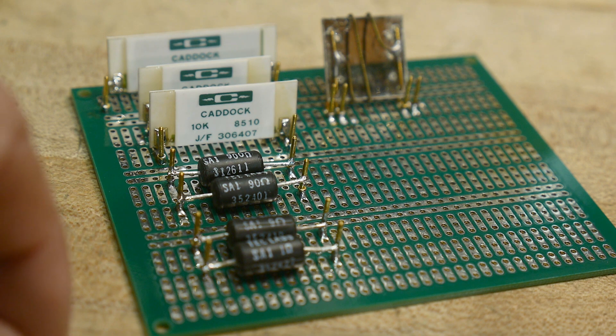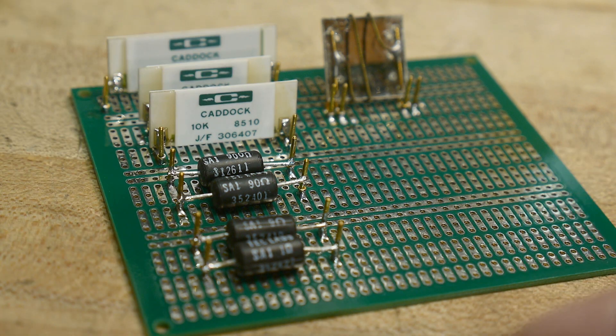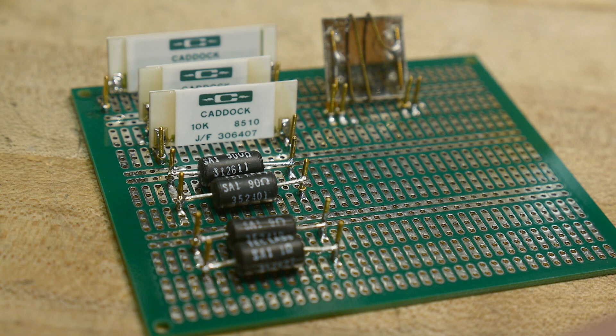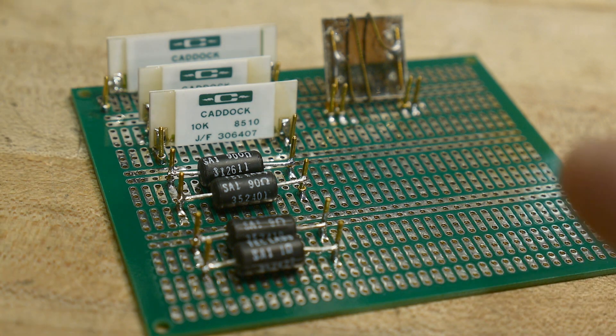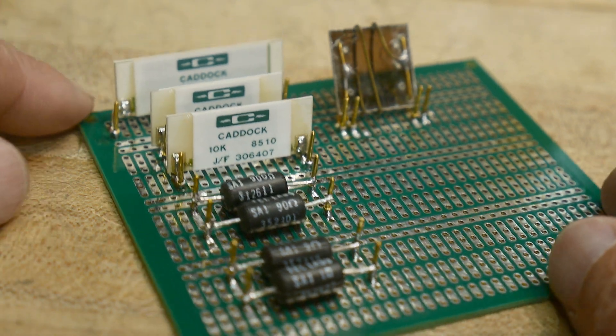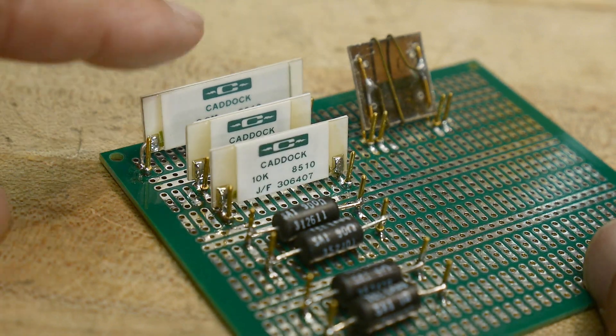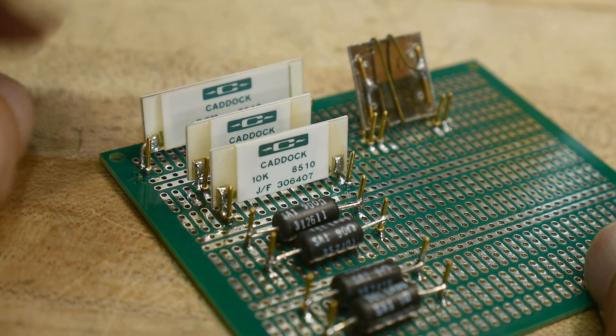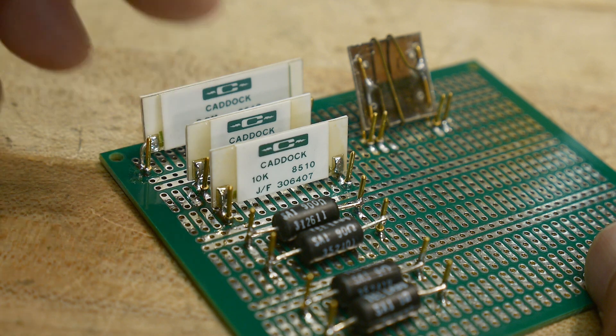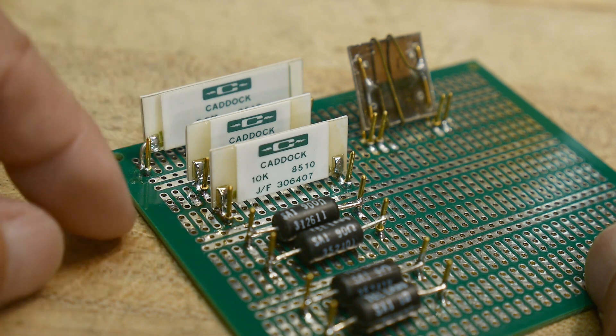Here are some precision resistors that allow you to use the calibrations at different voltages. These are Caddock, they're thin film on ceramic substrate, so these are real accurate.